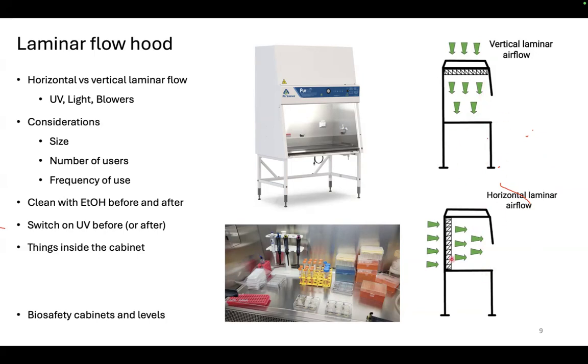So in this case, the user is not super protected. That is where these biosafety cabinets, which we're not talking about in detail today, come in handy. But out of these two, this one protects you absolutely zero because it's blowing air in your face or whatever is your exposed part. This one is still slightly better, but it still offers no protection to the user. Both of them are great to protect your sample, but again, you as the user are not protected.